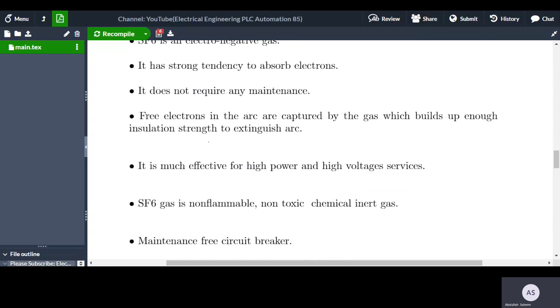So short arcing time. So what is arcing time? Arcing time is the time required by arc phenomena to occur. So in minimum arcing time, SF6 circuit breaker will extinguish arc phenomena due to the attribute which we have already discussed, that it is highly electronegative in nature and it has tendency to absorb electrons. It can interrupt much larger currents irrespective of the magnitudes of current. That is why SF6 circuit breaker is used on large scale, gives noiseless operation due to its closed gas circuit.